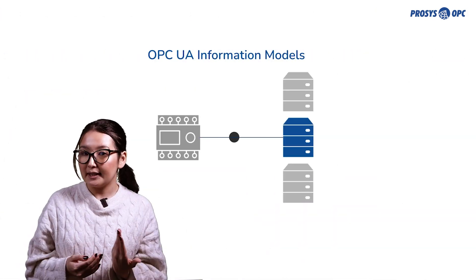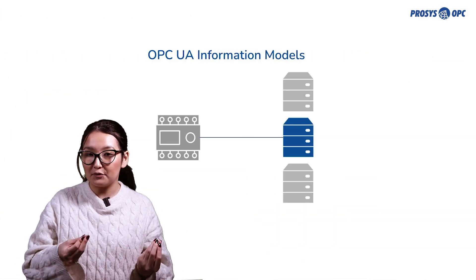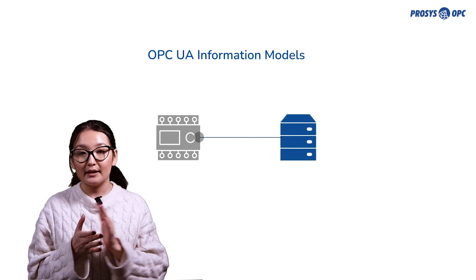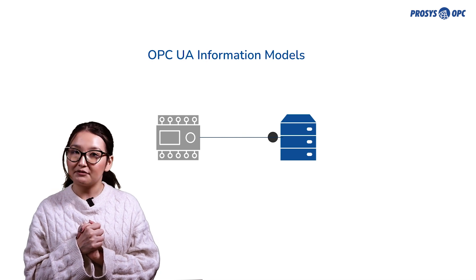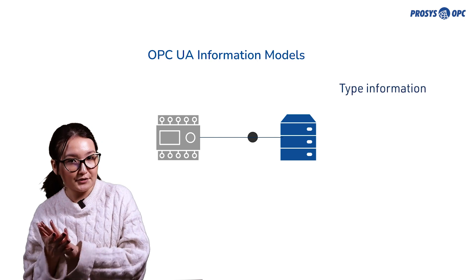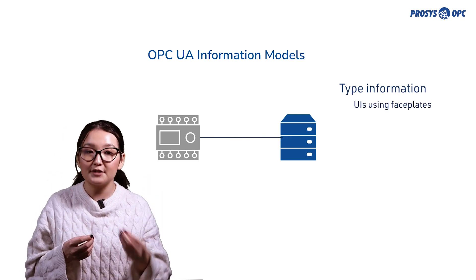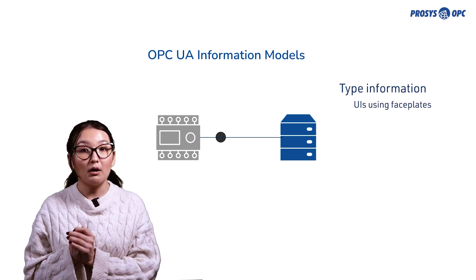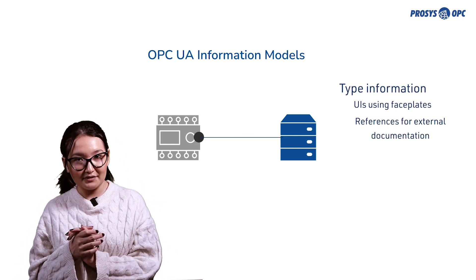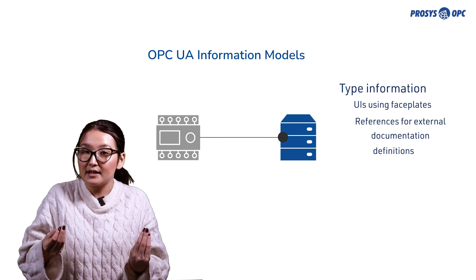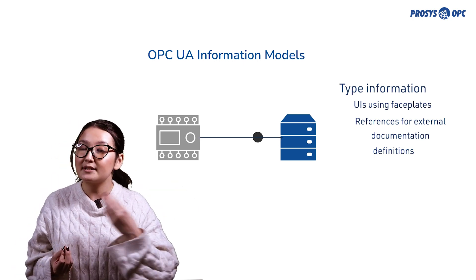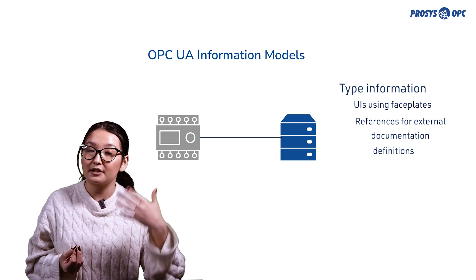In OPC UA, the address space became much more powerful. First of all, historical data and alarms can be directly linked to the measurements. The main improvement, however, is type information, which enables much more intelligent applications. You can prepare user interfaces with specific faceplates for well-known machine types. Also, you can use references to create external documentations or definitions. All this can help a lot with integrations going towards automatically configured production lines in a plug-and-produce manner.